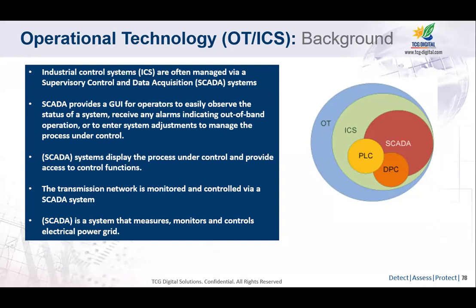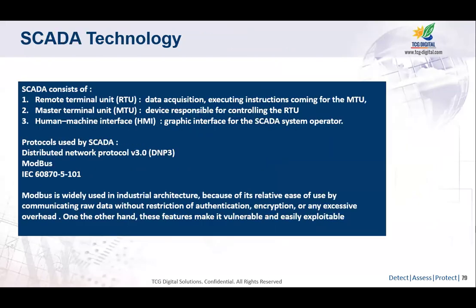The transmission network is also monitored through these systems. It measures, monitors, and controls the electrical power grid - you can see the diagram on the right-hand side. SCADA consists of RTU, MTU, and HMI. I've already shown you the HMI. The protocols used are DNP, Modbus, IEC 60870.